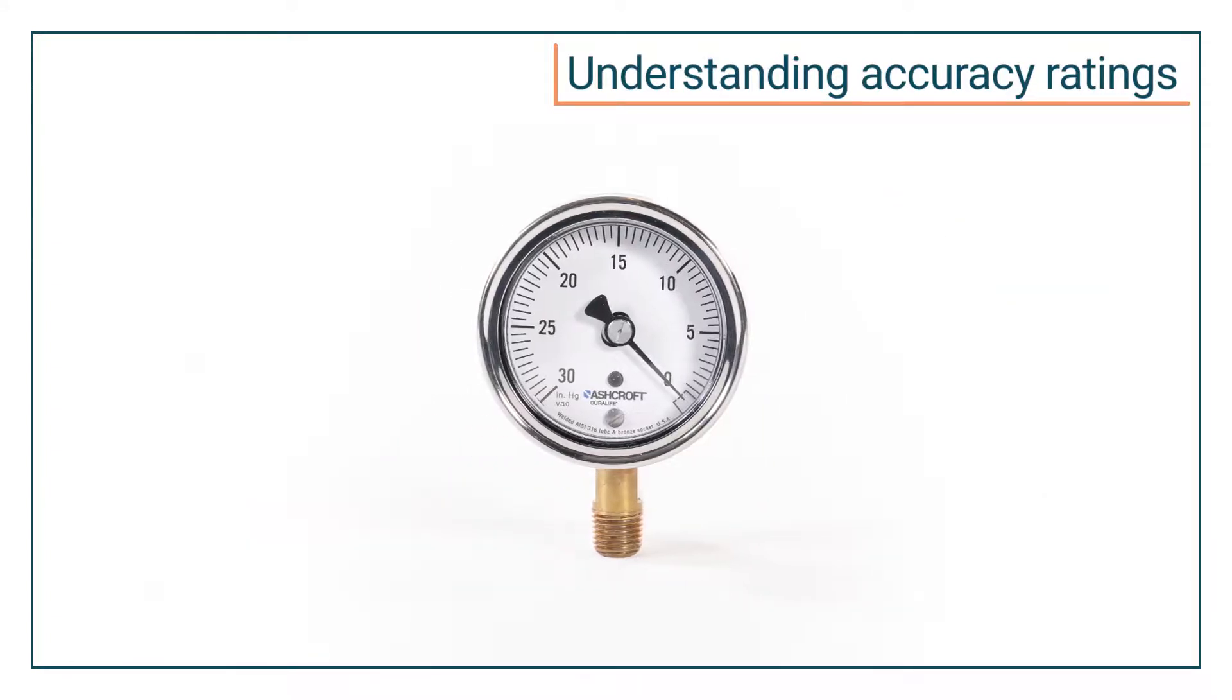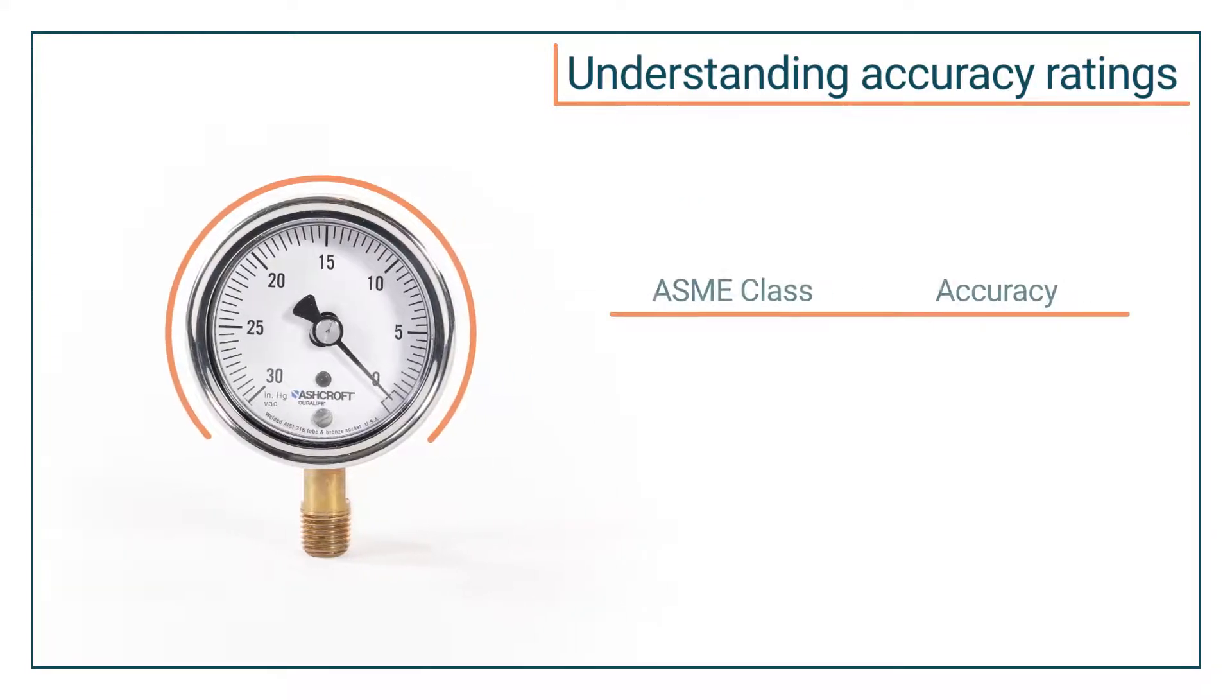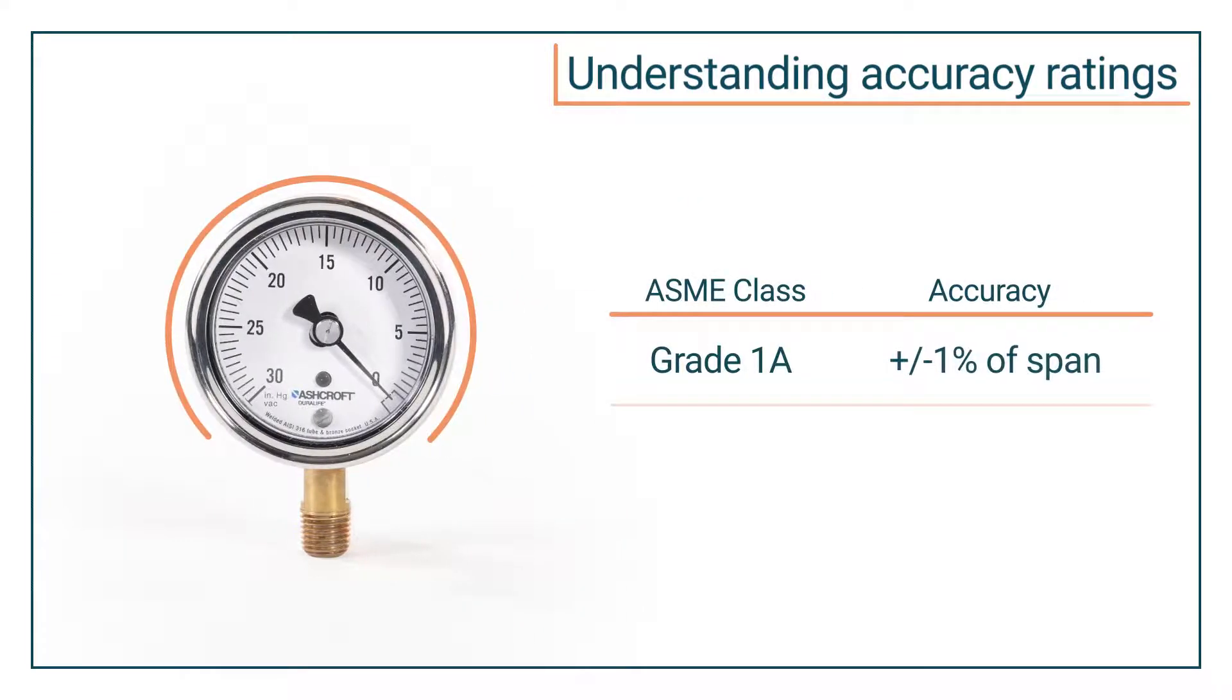Full range gauges will have a single number used to express accuracy across the entire span of the gauge. For example, plus or minus 1% means that the measurement will always fall within plus or minus 1% of the gauge's range.